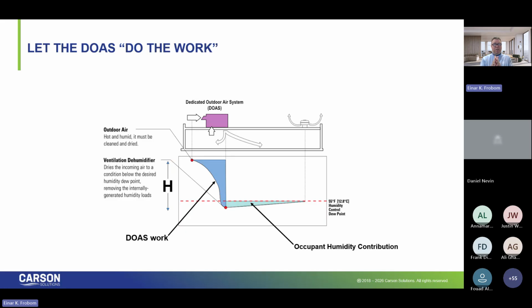And the key point here that we emphasize in our system design is you need to look at the design dew point condition of your outside air. Don't just look at your design cooling day, look at your design dew point day, because that will have more moisture and more energy. And if you don't capture the design dew point day in sizing your DOAS, you will undersize it by about 10 to 15% in your market. I'm out of Minneapolis, by the way, so we're very similar markets in terms of climate.